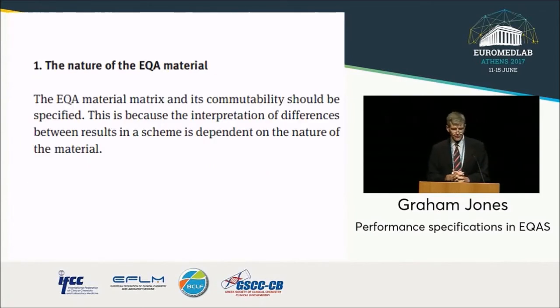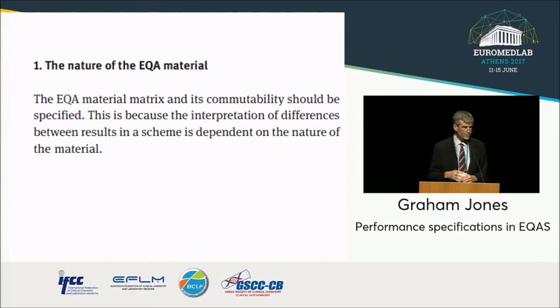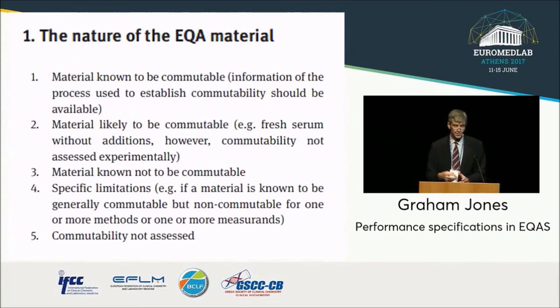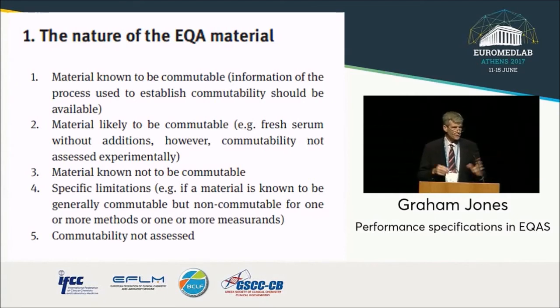The first element is the nature of the EQA material — you need a statement from your EQA provider that describes the material in a way which allows you to understand it. The particular key question is: is it commutable or not? If you're looking at results from two methods and the material is not commutable, you are unable to make a valid assessment. If the material is known to be commutable, then you can. Statements might say it's known to be commutable, likely to be commutable such as fresh frozen serum, known not to be commutable, or that it simply hasn't been assessed.